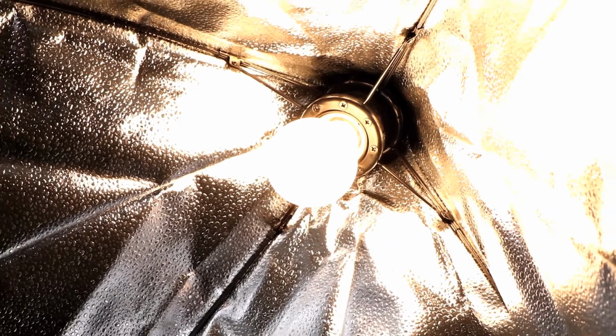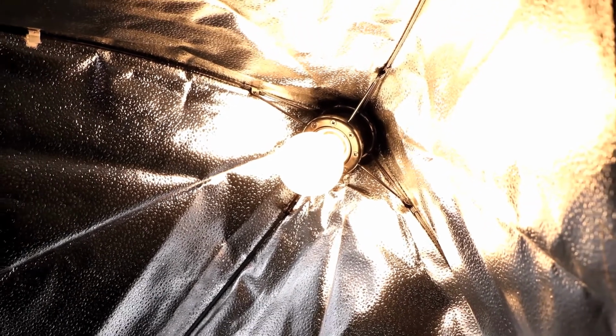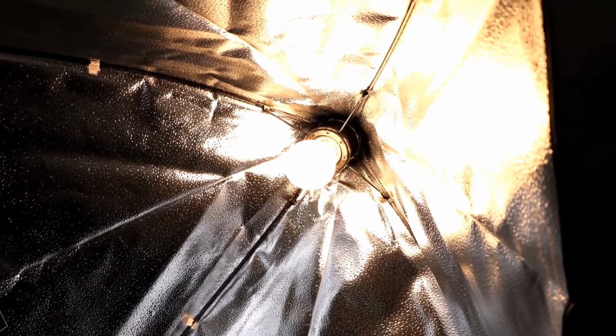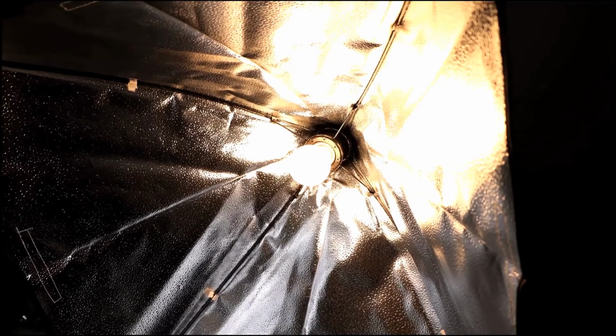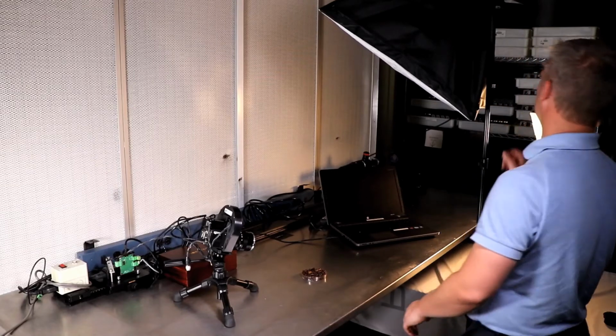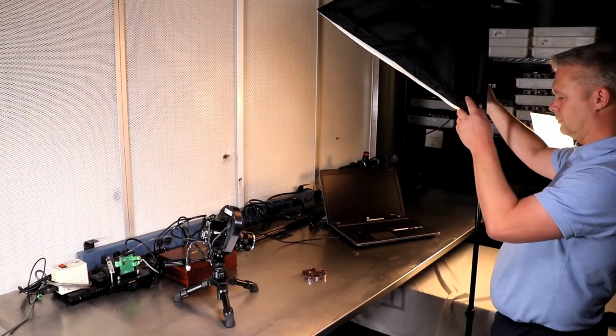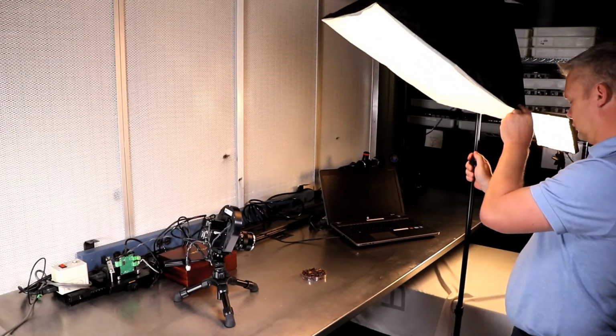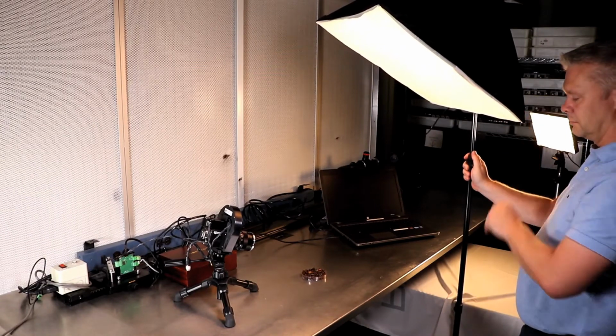For a proper spectral imaging measurement, an adequate light source needs to be chosen, with optical output in the same wavelength range as the filters installed in the camera. Be sure to create a diffuse lighting environment to avoid specular reflection from the objects you're trying to characterize.